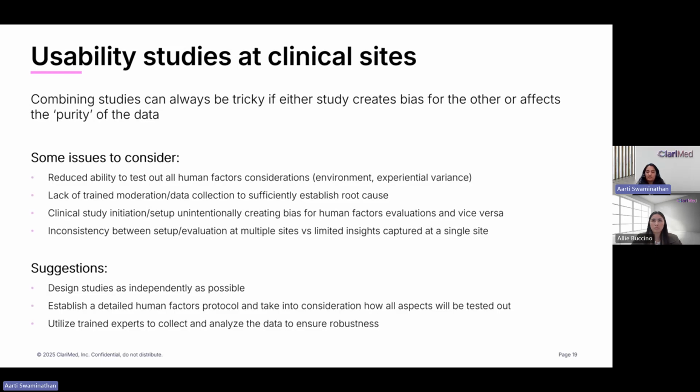And I think it really depends, and we like to joke that for all human factors answers, we always begin with it depends, but that's really the case, that every product is slightly different. So it would really depend on what that test is diagnosing, what that process looks like, how much user interaction there is, and how much power the user has to create serious harm by making a user error. The other thing is, like I said, the FDA tends to pay more and more attention to human factors the less trained users are.